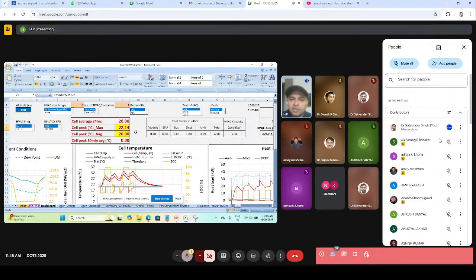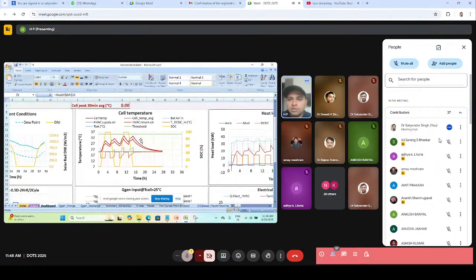For battery energy storage, the more popular configurations are 2 hour, 4 hour, and even 8 hour. When I say 2 hour, 4 hour, 8 hour, I mean, if I have a 5 megawatt hour equipment deployed at site, we might be dealing with an application where, when there is no power, the customer needs a consistent 2.5 megawatt power for 2 hours, so I call it a 2 hour application. We have to run the equipment continuously for 2 hours, discharging and supplying electricity to the customer. If it's 4 hour, it has to run for 4 hours, and the same 5 megawatt hour would supply half of 2.5, so 1.25 megawatt to the customer for 4 hours. And likewise there are 8 hour applications.